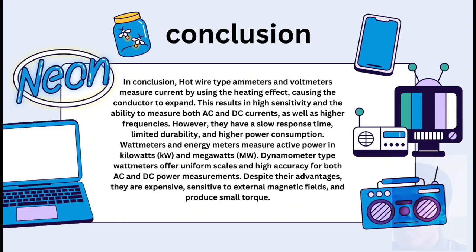Lastly is the conclusion. In conclusion, hot wire type ammeters and voltmeters measure current by using the heating effect, causing the conductor to expand. This results in high sensitivity and the ability to measure both AC and DC currents as well as higher frequency. However, they have a slow response time, limited durability, and higher power consumption. Wattmeters and energy meters measure active power in kilowatt and megawatt. Dynamometer type wattmeters offer uniform scales and high accuracy for both AC and DC power measurements. Despite their advantages, they are expensive, sensitive to external magnetic fields, and produce a small torque.